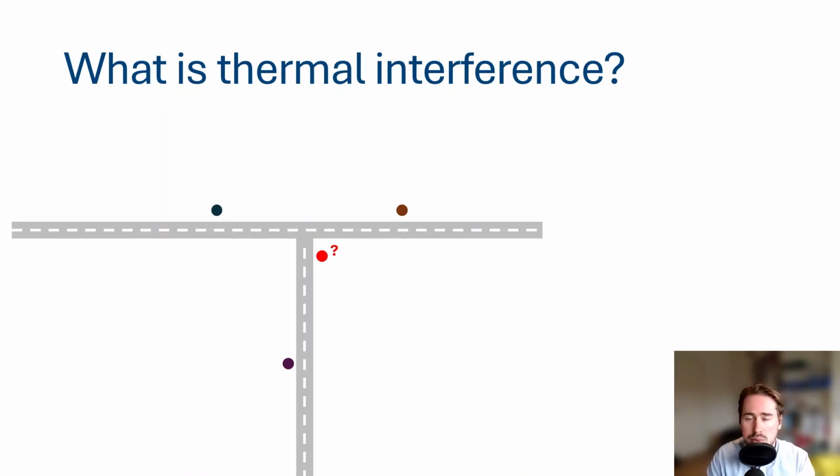So what we do is we fire up GHEtool, we fill in the ground parameters, we make our design, we fill in our building demands, and we end up with a temperature profile. We make sure it sticks within certain limits, and we can make our official offer. We can say, well, this is the amount of drilling borehole meters you need. Now, of course, that does not take into account the fact that there are neighbors here.